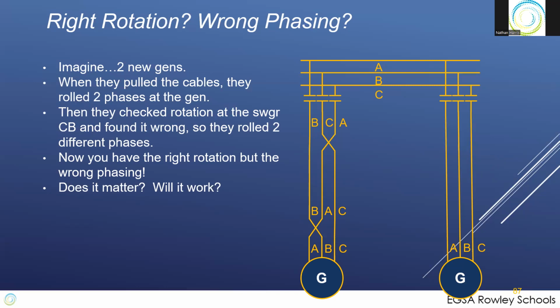Your rotation is correct, and it will work. If you're paralleling 2 machines, this will work. Where it'll bite you is that, let's say you're working on a system one day and you're looking at different currents and different phases. The A phase current on this machine is not the same as the A phase current over here, because A phase rolled over here to C. So now you've got to look at A phase. Say you want to balance currents in the machines, you've got to balance between A and C.